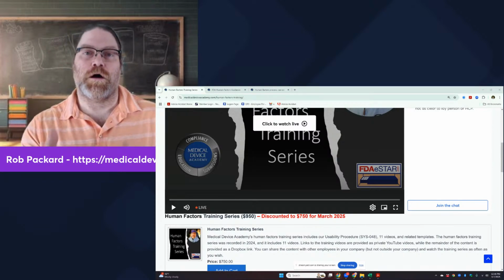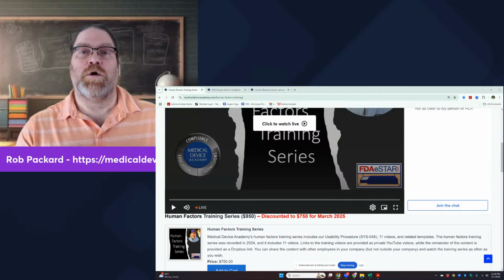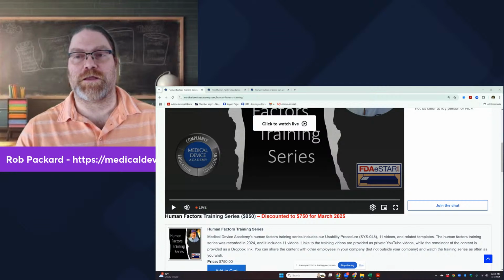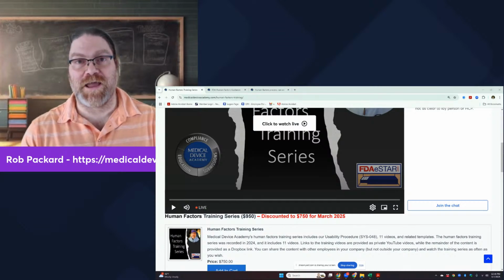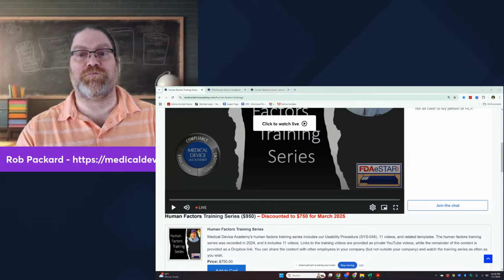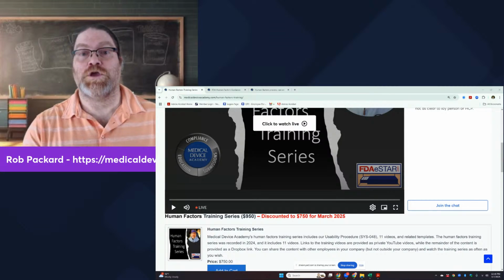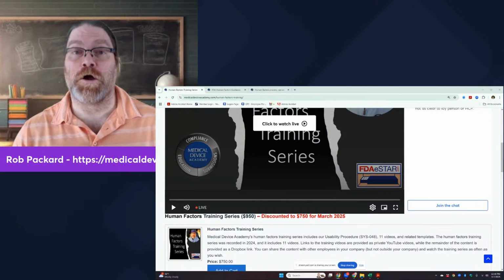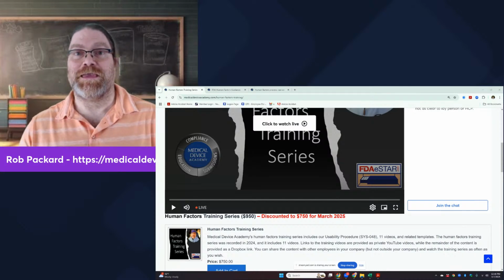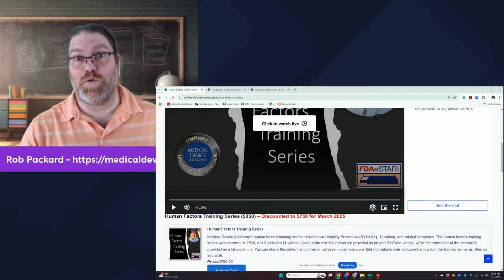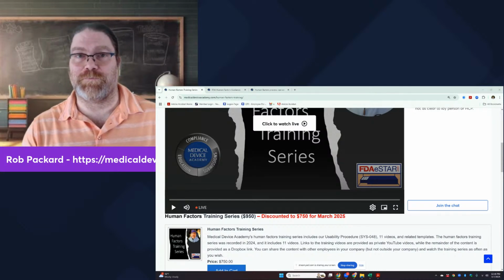So on the point of IFUs, or instructions for use, one of the things that I tell people, they're like, well, do we have to finalize our instructions for use before we do the testing? Yes and no. You'd like it to be final, but part of the reason why you're doing the testing is to see if it's final or there are still some use errors, things that need to be clarified.